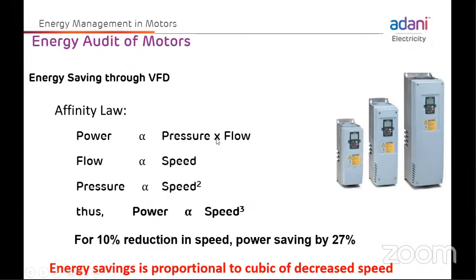So definitely, power is proportional to pressure into flow, and flow is proportional to speed, and pressure is proportional to speed square. Thus, simply power is directly proportional to the cube of speed. That means a 10% reduction in speed gives a power saving of 27%. So energy saving is proportional to the cube of speed.